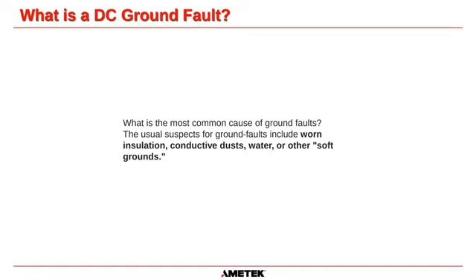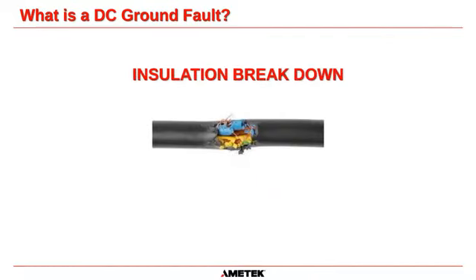So, what is a DC ground fault? Well, the most common cause of ground faults is worn insulation, conductive dust, water, or other soft grounds. So, obviously, insulation breakdown. Insulation is the plastic or rubber that is containing the conductors in the system. You can see the copper here, the copper here, and the copper here. So, this insulation has broken down, and these strands of copper wire that are supposed to be going to the load circuits can now touch a metallic object outside, whether it's a cable tray or something that it's mounted to, and can touch ground. That is the first way that we can have a ground fault, through insulation breakdown.